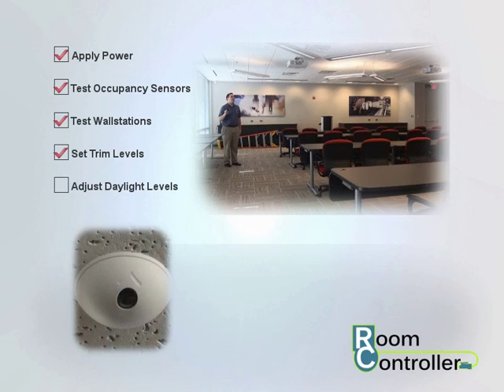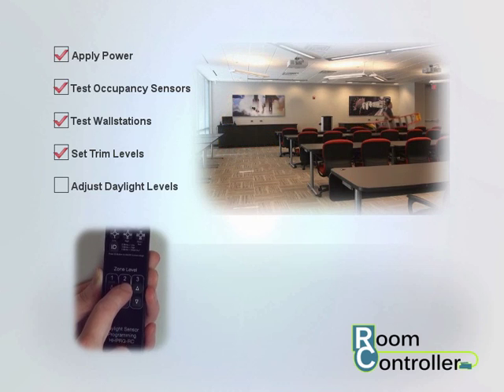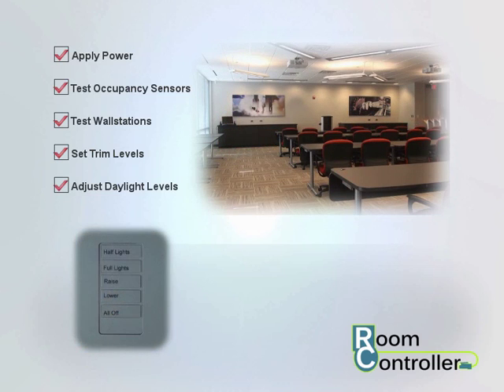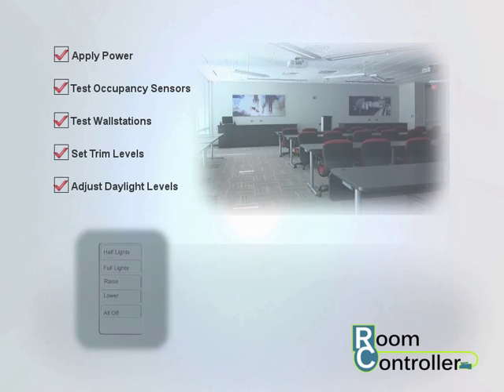The daylight sensor's green LED will start flashing rapidly. Repeat this process for each of the dimming zones that need adjustment. Once the daylight levels are correct, press the All Off button on any wall station. If All Off is not pressed, the controller will save the settings and exit commissioning mode after 2 minutes.